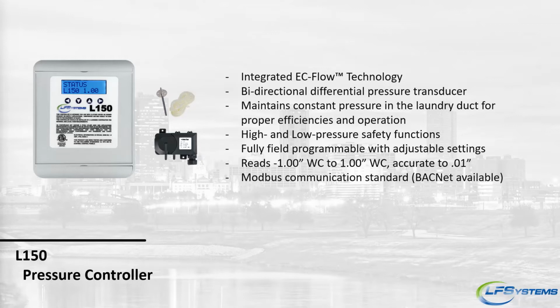There are adjustments that can be made if your sensor location isn't optimal, or if it's a shorter building or a taller building, we can adjust the PID loop accordingly. And Modbus is standard if you have a BACnet, or if you have a BMS system. Yes, we can use BACnet through a gateway, but that way you can see the status of all your fans and all your shafts on your BMS.